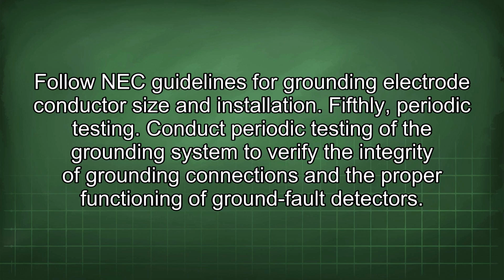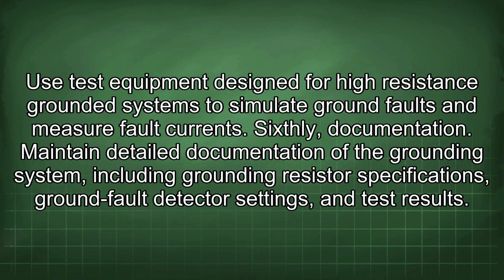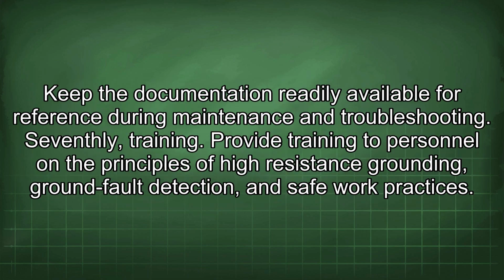Fifthly, periodic testing. Conduct periodic testing of the grounding system to verify the integrity of grounding connections and the proper functioning of ground fault detectors. Use test equipment designed for high-resistance grounded systems to simulate ground faults and measure fault currents. Sixthly, documentation. Maintain detailed documentation of the grounding system, including grounding resistor specifications, ground fault detector settings, and test results. Keep the documentation readily available for reference during maintenance and troubleshooting.